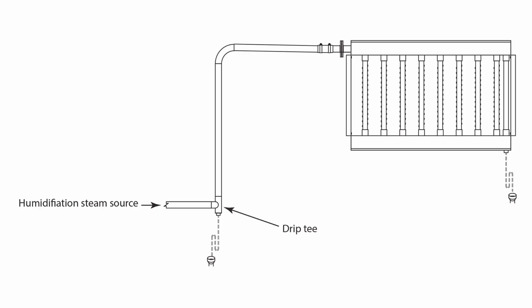Okay. When we're thinking about getting steam up to the dispersion system, what are some of the considerations I need to be aware of? If it's in a boiler, you want to make sure you're getting relatively clean steam. You don't want to take off the bottom of the steam main where you've got condensate rolling through it. It's a little different application, but you want to make sure you have drip tees and such to remove any entrained condensate so the dispersion device can handle it. You might as well mitigate it first and make it work optimally.